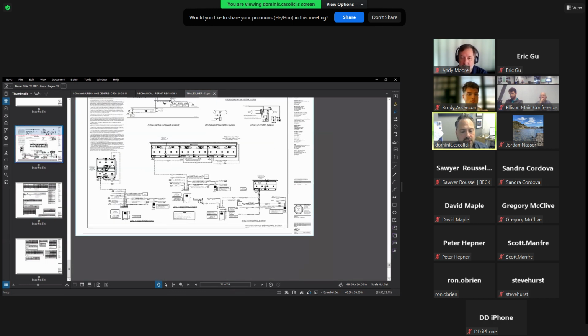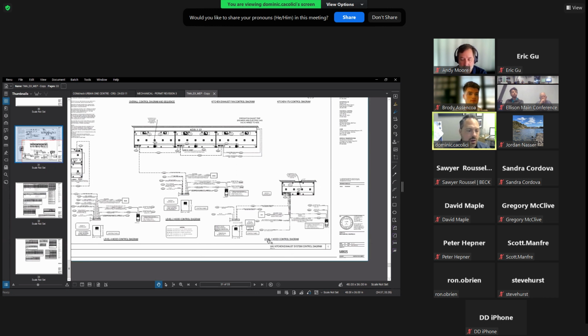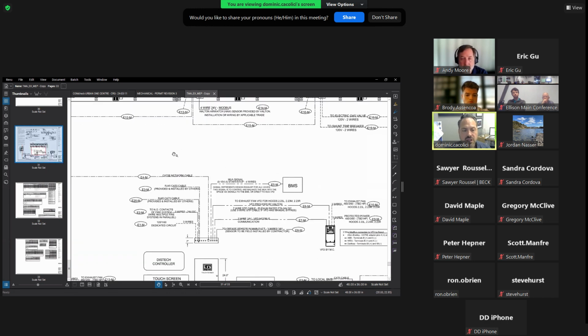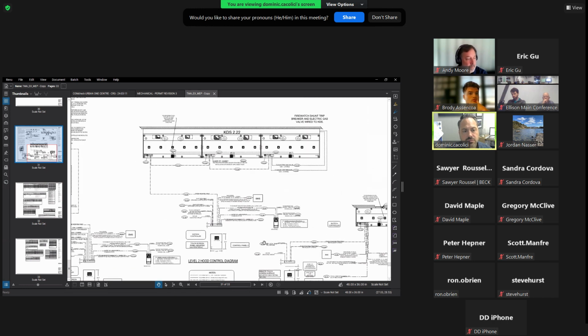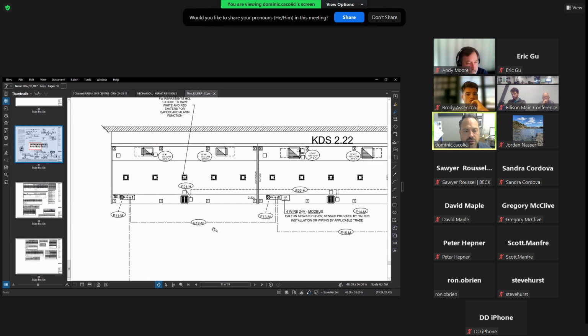One thing we did that you should be aware of is we recreated the Halton kitchen hood control diagrams. The breakaway is they're going to provide you with the control devices and the controllers, but then you guys have to wire it up, so that's why that's all on here. We did our best to show a cutoff of who does what, so everything is coordinated to the best of our ability with the manufacturer. There is a secondary manufacturer you can go to, but again, this was all coordinated around Halton. So it's really important that you understand how this system is designed and has a UL design for these CFMs. If you deviate from that, things cascade into another direction, so it's really important that we keep that in mind.